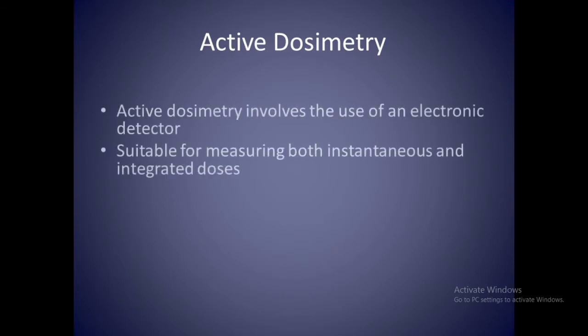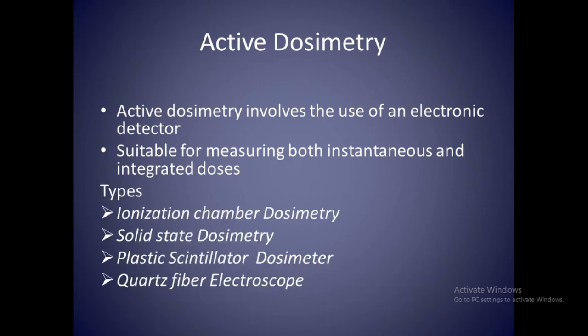Some of the commonly used passive dosimetry techniques include thermoluminescent dosimetry, optically stimulated luminescence dosimetry, film dosimetry, and track etch. Active dosimetry involves use of an electronic detector and is suitable for measuring both instantaneous and integrated doses. Commonly used active dosimetric systems include ionization chamber dosimetry, solid-state dosimetry, plastic scintillator dosimeter, and quartz fiber electroscope.